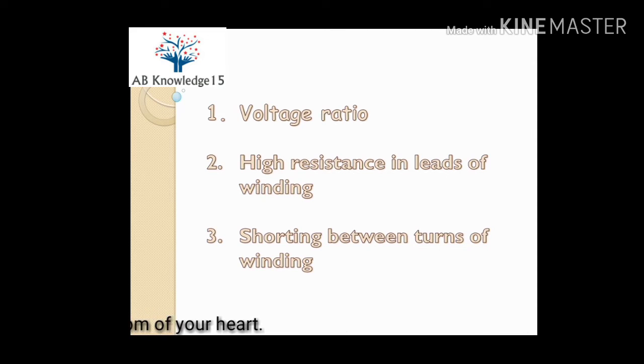So note down here the three purposes of this test: first is the voltage ratio confirmation as per the nameplate; second is checking for any high resistance in leads of the winding of transformer; and third is to find any shorting between turns of the winding of transformer.